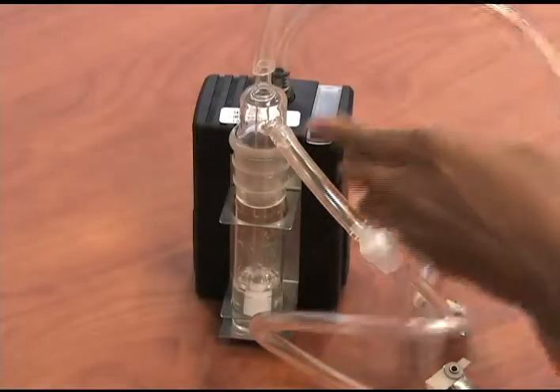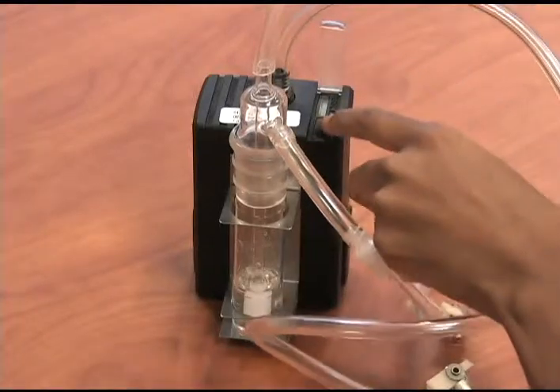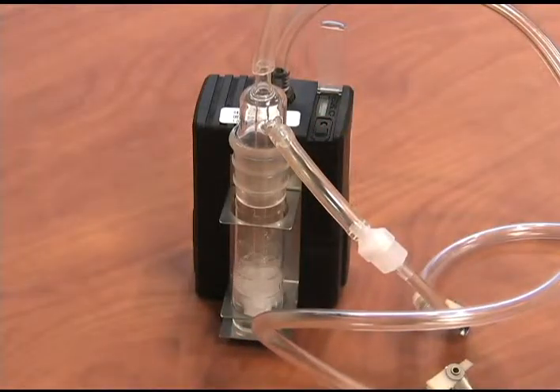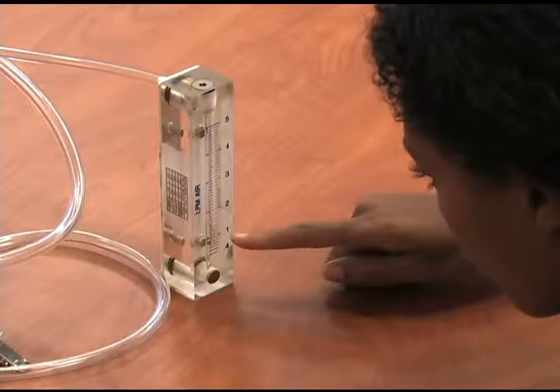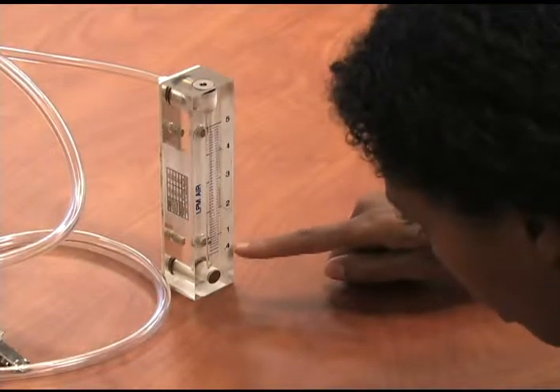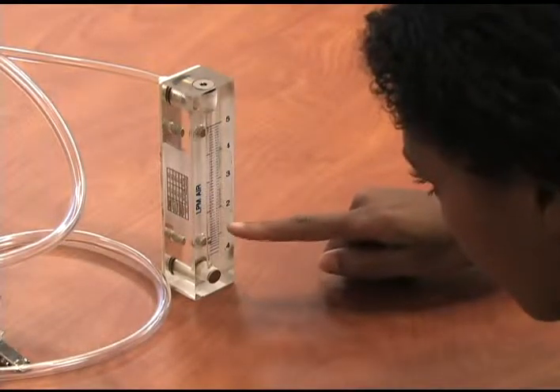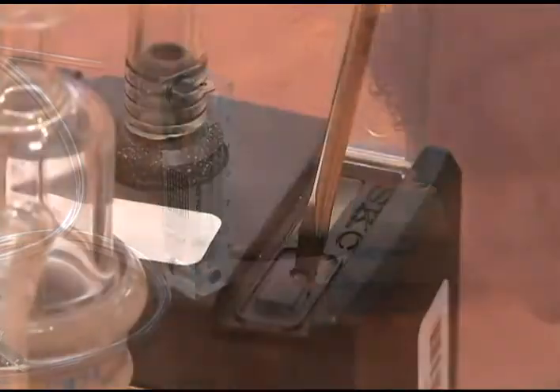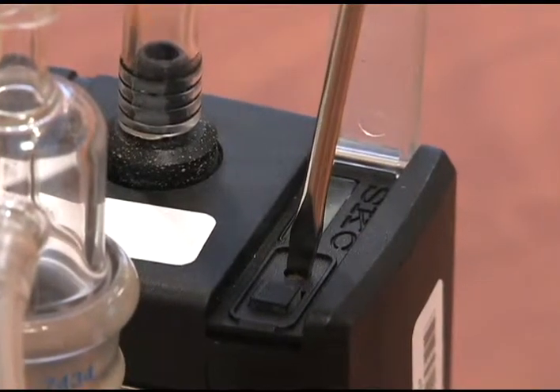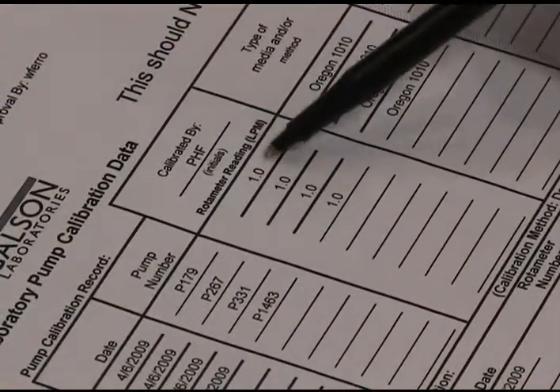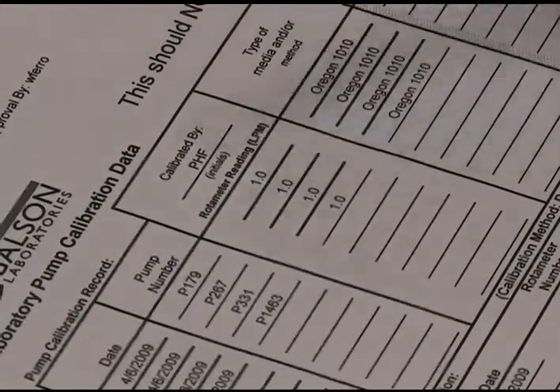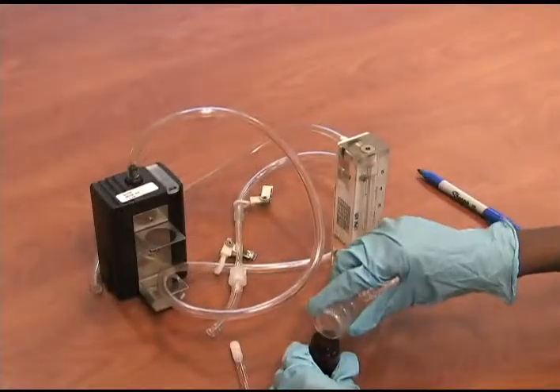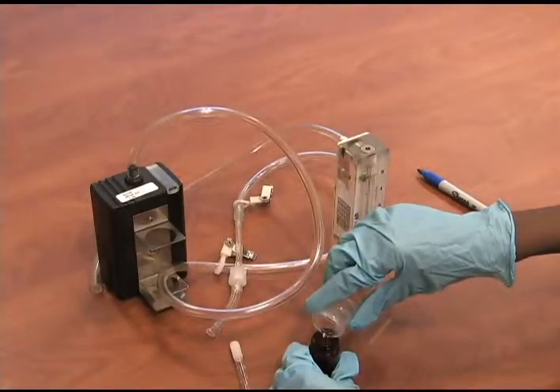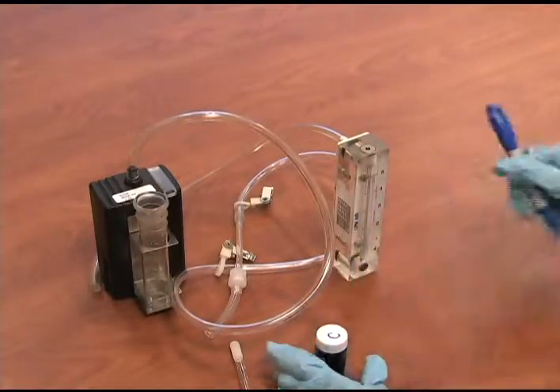To begin calibration, turn on the pump. With everything sitting on a level, flat surface, check the ball float in the rotameter. Be sure to take your rotameter reading at eye level and use the center of the float for the value. If you need to adjust the flow, use the set screw on the pump. After you are satisfied with the flow rate, turn off the pump and verify the recorded value on the pump calibration sheet. Carefully transfer the solution into the vial, cap, and mark for calibration.